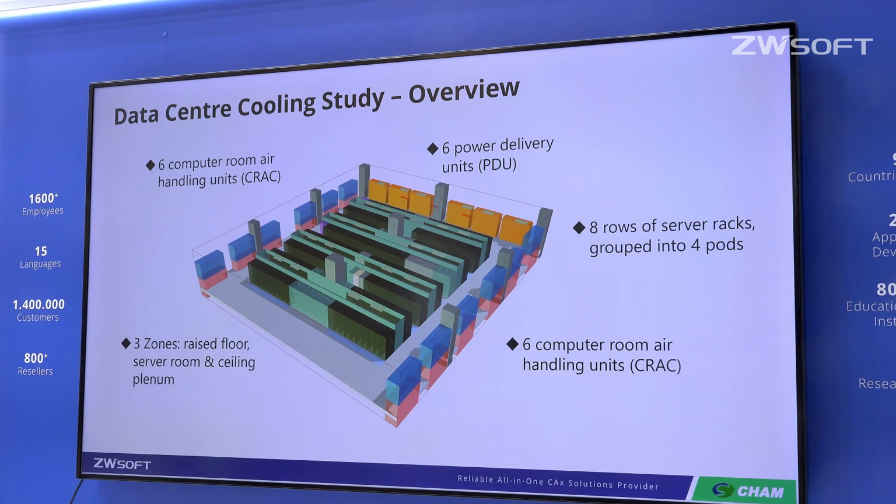A particular feature of this data center is that the power distribution units that were chosen do not connect to the ceiling. This was a restriction that the designers had to adhere to due to some infrastructure constraints, which meant that they could only have the units on the far wall, and they needed to be situated close together in order to accommodate their size. So they just issued their waste heat into the room, which is something that we'll look into in a little bit.